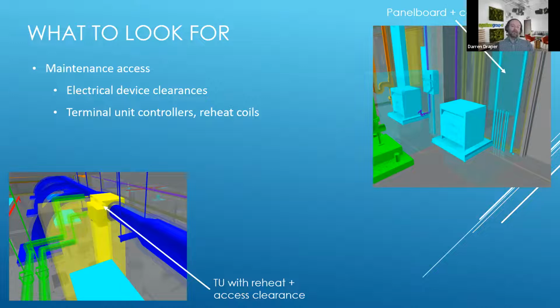But that doesn't help you when you've got to get up to it. You could have it clear if you model that maintenance clearance outward, but we expect to see it modeled in the vertical as well - take that entire maintenance clearance down. You still have to get on a ladder to access the controller, the reheat valve actuator, the circuit setters - all of those require access. If we don't model that vertical clearance, we'll often find there could be something below in the plenum space, though usually that's avoided. It's things that go below the ceiling, like furniture or fixed casework that can't be moved.